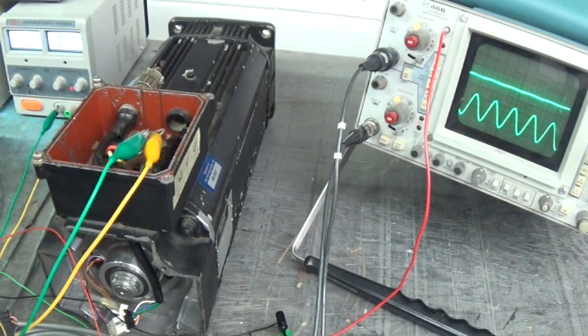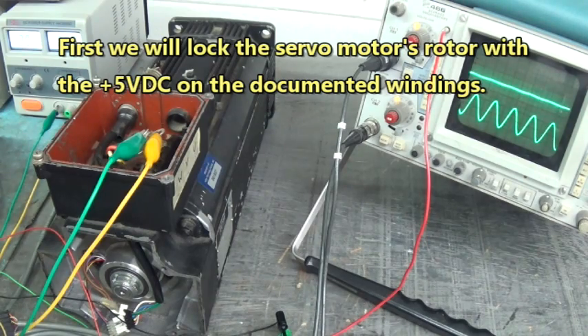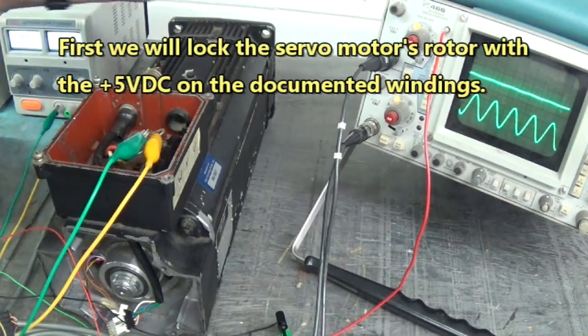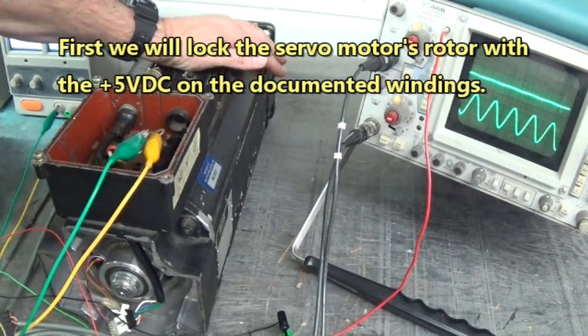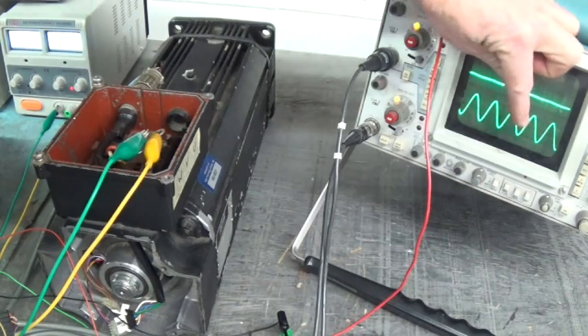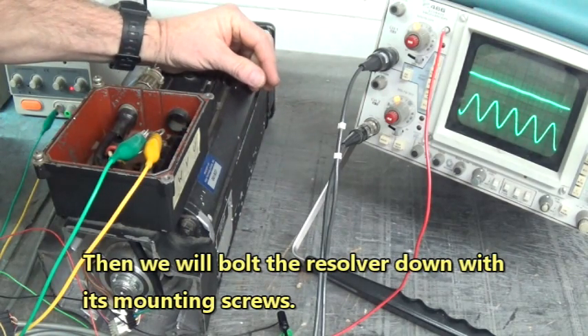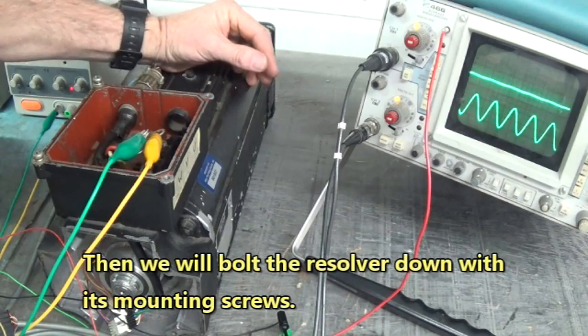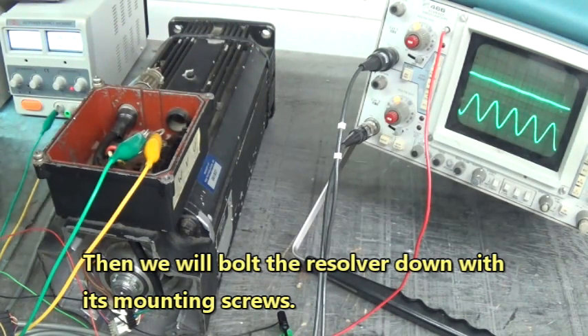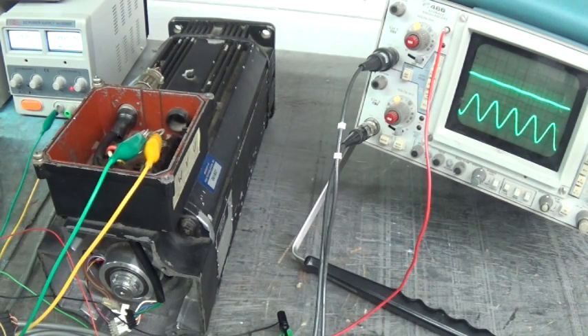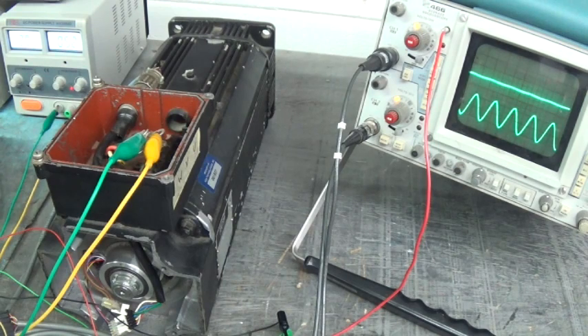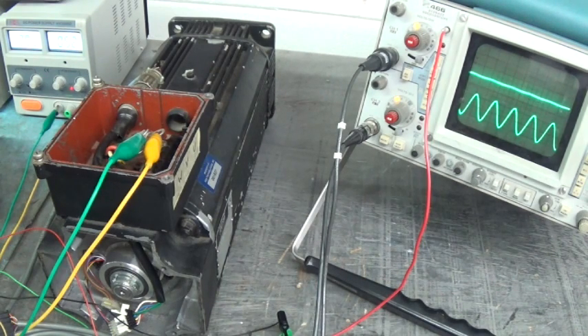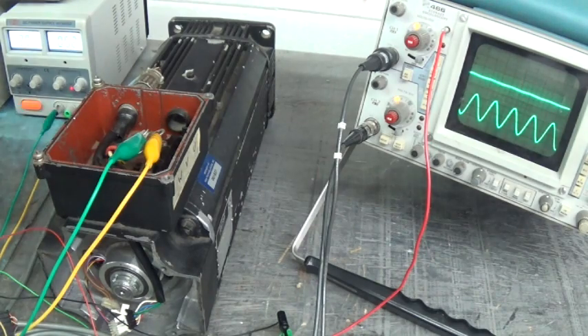So now when we put this back together, we'll write all this down and it has to be hooked up exactly the way you took it apart. And when we go to put that resolver in here, we'll rotate it until the sine is flat line and the cosine is at max amplitude. There you go, that's a neat little trick if you ever have to take a resolver off the back of a servo motor. Hope you enjoyed that, that was a lot of fun.